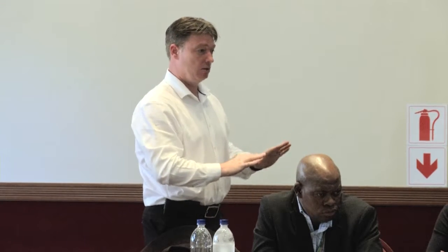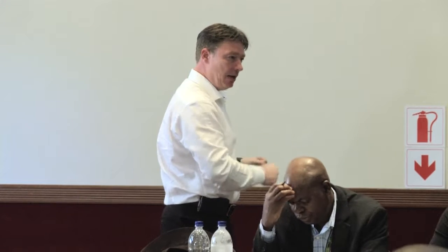Okay? Yes. So if I've got a lekker open space and I want to be very scientific about it, I can use the SANS standard and say this piece of equipment on its own, free field, gives me this one. Now, there's a big difference between a free field measurement and a workplace measurement because of cumulative noise, background noise, reverberation, size of excavation. And I can go on and on. So what this document tries to do is take the principles of the SANS standard and apply them to an underground working environment. So it will never be exactly the SANS standard, but it tries to make it practicable underground, how to do it best.